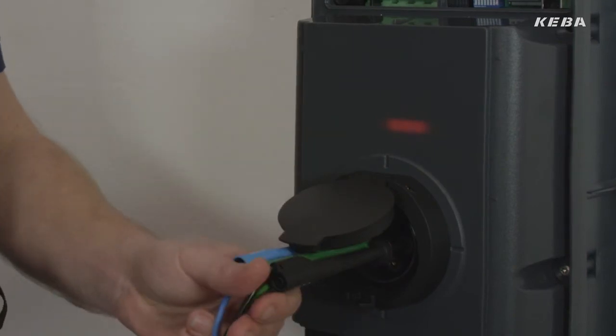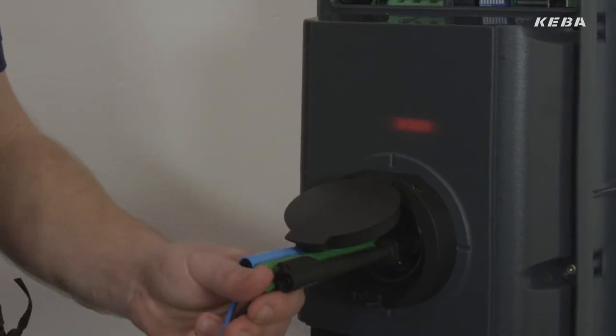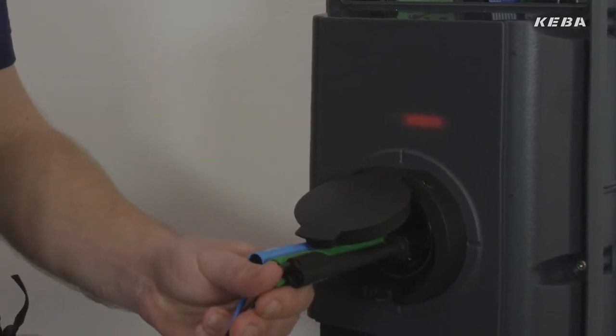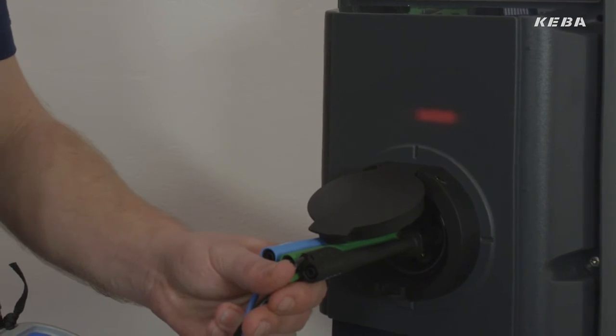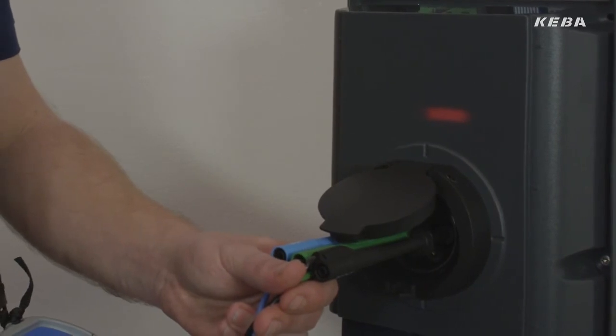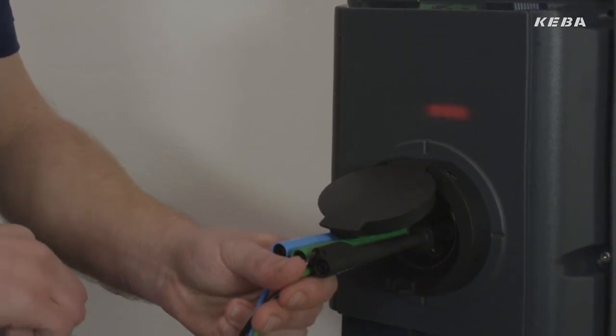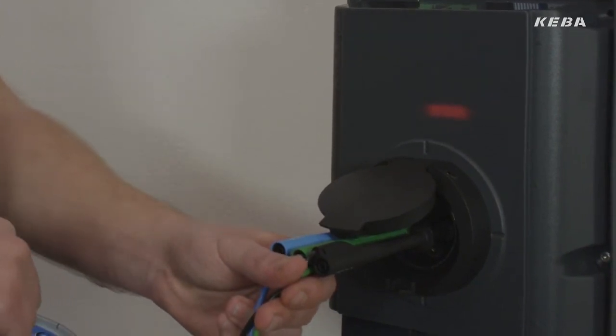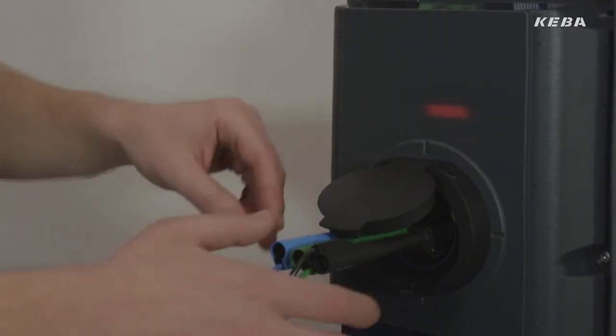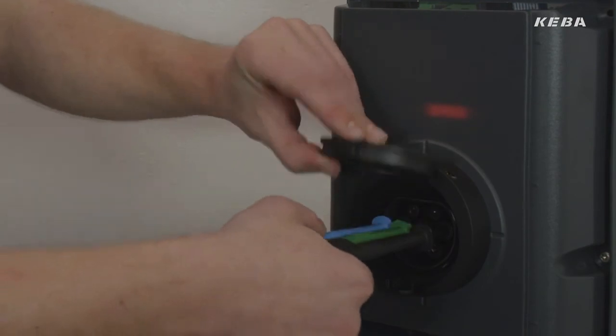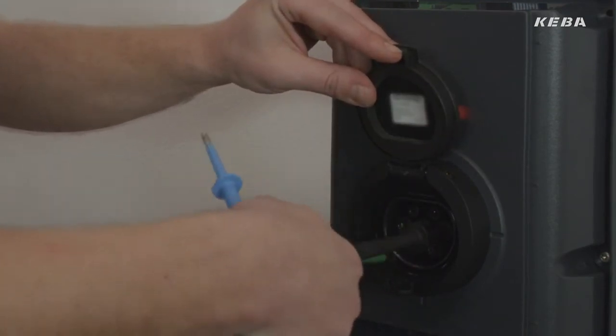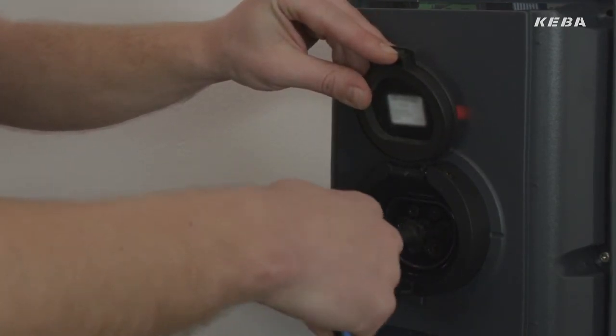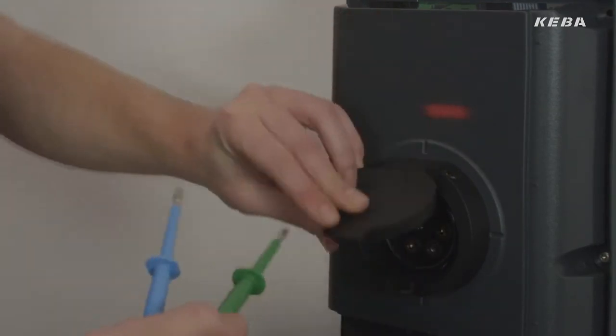An orange LED indicates that the wallbox is in commissioning mode. In this mode, the effectiveness of the installation's safety measures can be tested according to national regulations before the unit is used for the first time.